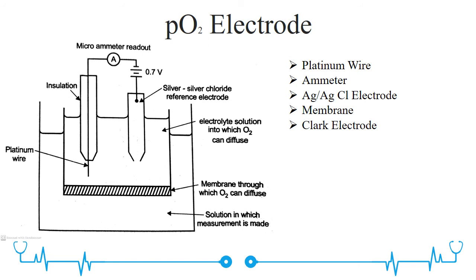The oxygen electrode is used to monitor the partial pressure of oxygen in biological fluids. Similar to the pH electrode, the oxygen electrode is available in an integrated version consisting of the platinum cathode and reference electrode in the same enclosure, called the Clark electrode.